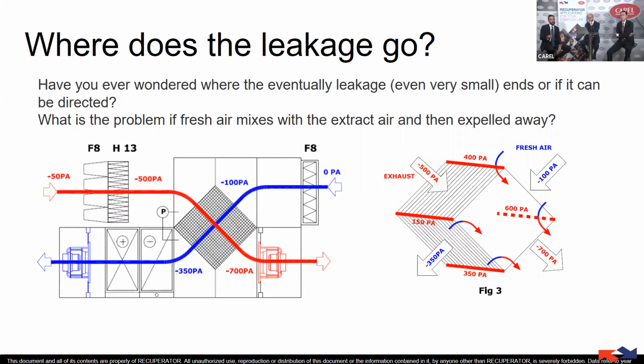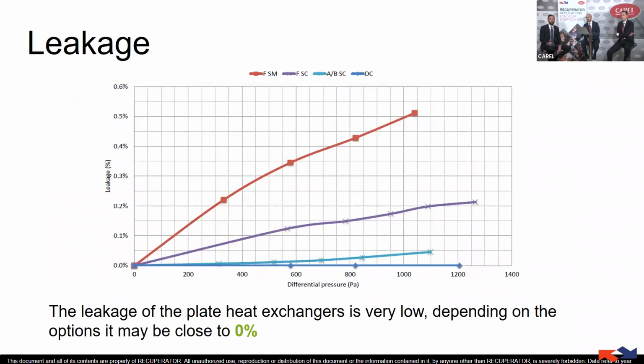One main answer was cross-contamination. Cross-contamination is not the same as leakage, but with the right differential pressure we can give a direction to the leakage. If the leakage goes from supply to exhaust, then we don't have cross-contamination. So it's really important to understand how to direct the leakage to avoid any type of cross-contamination. But in the case of the plate heat exchanger, as it is built from plates joined together, we can anyway have a leakage that is really, really low.